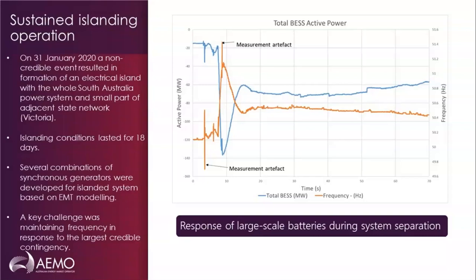We never had such a long islanding condition, and combined with relatively mild weather, but as you can imagine, January and February are summer here in Australia, which meant fairly sunny conditions as well as windy conditions, and how to manage and operate this system with such high levels of inverter connected generators that is now islanded, meaning that there is no support at all from the adjoining networks that would otherwise be possible. We have developed and implemented almost on the fly a range of measures based on detailed simulation studies on how to manage system security under these conditions, which might warrant a separate presentation at a different time.